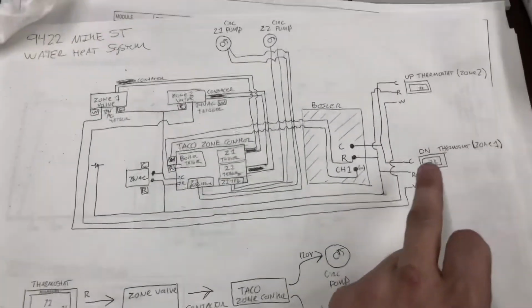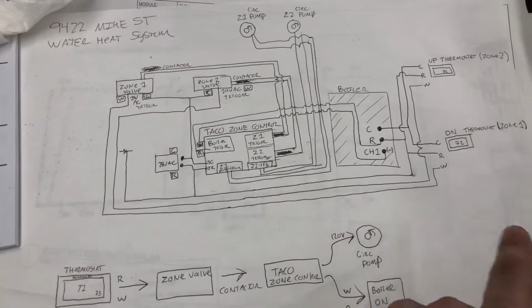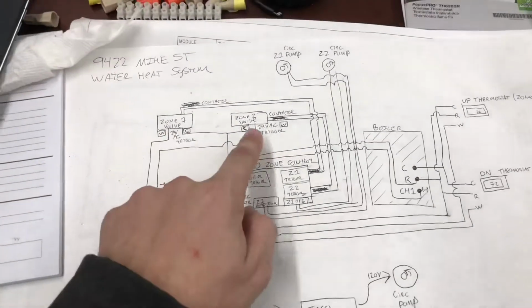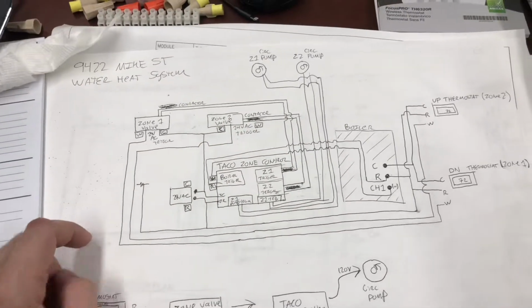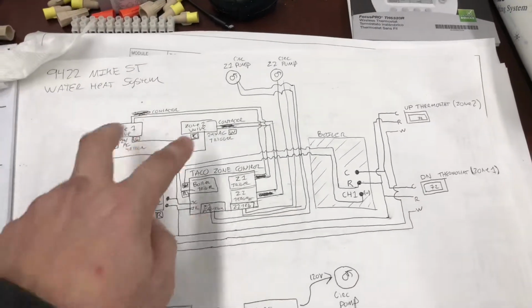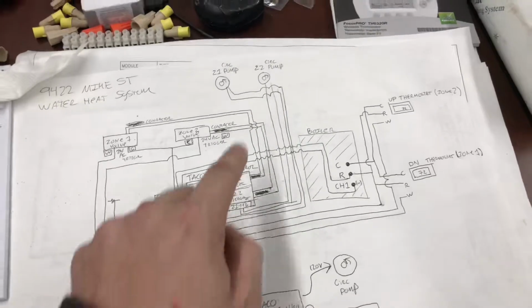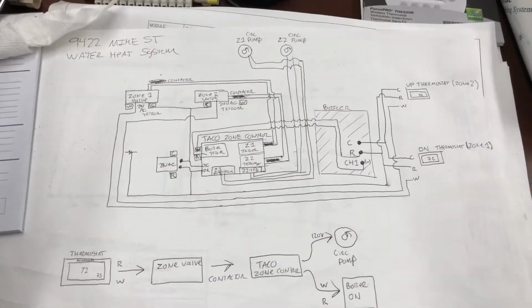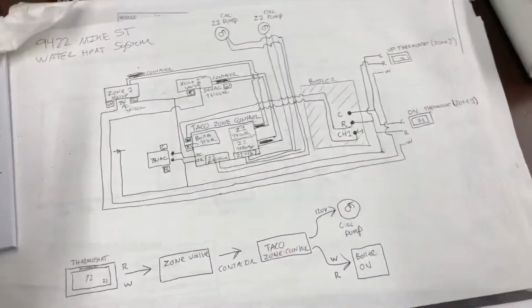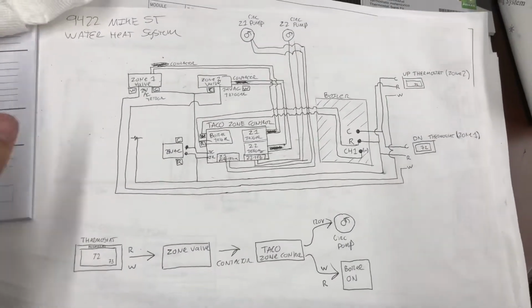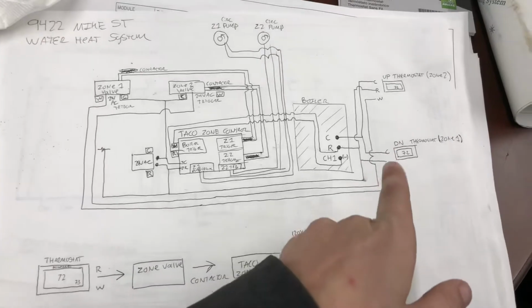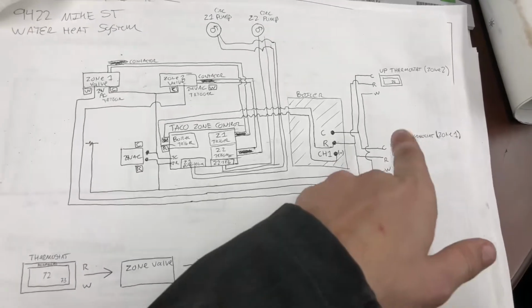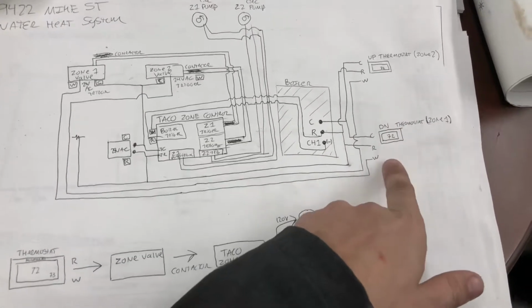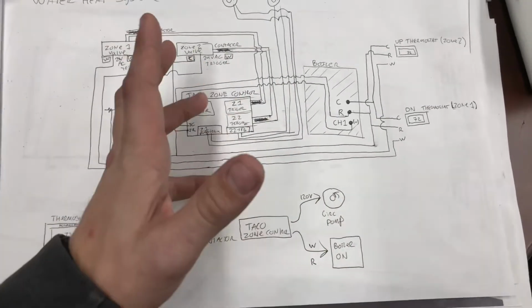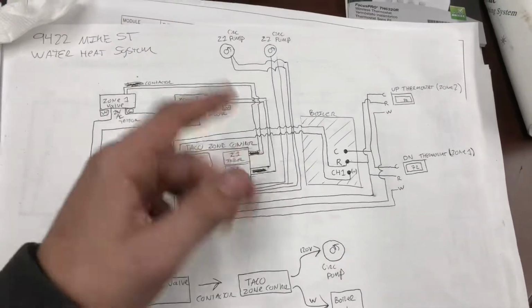So all we're really doing is using thermostats to trigger the zone valves. So we're using the W's on the zone valves for that. The zone valves are then triggering the taco. The taco is then triggering the pump and the boiler. And Bob's your uncle. There's your heat. So again, if you freeze frame this and follow it, this is how you set up Honeywell Wi-Fi thermostats or any modern thermostat to control a multi-zone hot water system.